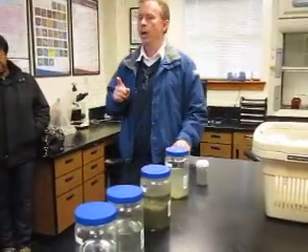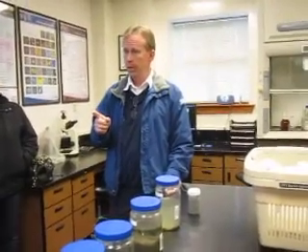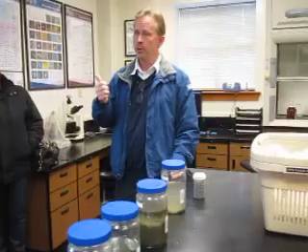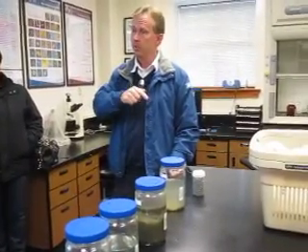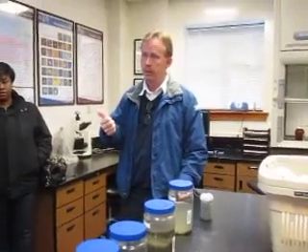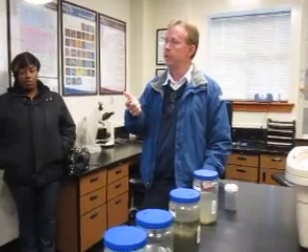We actually do that when we start having problems with our pH. If our pH gets too low or too high, the operators collect samples at strategic points in the plant, come back in here, test the pH, run a specific conductivity, and run COD tests.